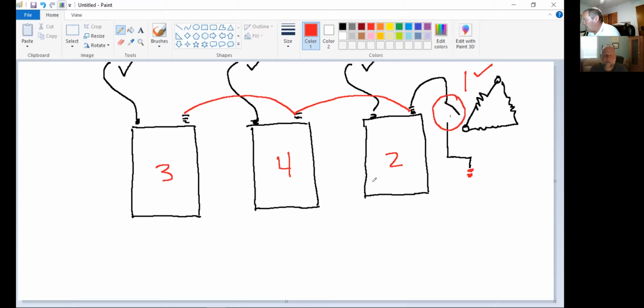So after 1, 2, 3, 4 on the de-energize - whatever we needed to do it for, say repairing secondaries or the customer wanted their power cut off - we would just leave switch 1 closed. On the re-energize, we would do 1, 2, 3, 4 for the close. Because now I'm going back to normal operation.